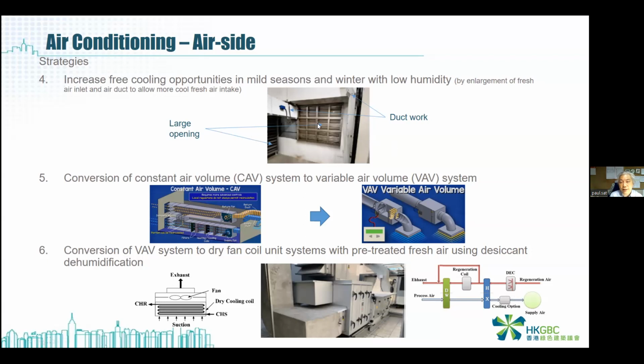Here you can see they have ductwork, which is the conventional design, and they also enlarge the outdoor openings so that they are larger. When the mild season or winter conditions are good enough for free cooling, which we call natural ventilation, they will open this kind of opening instead of using ductwork. But in summer they still use ductwork for cooling. This is what we need to modify, the openings of the building envelope, or we need to do it when we construct a new building.